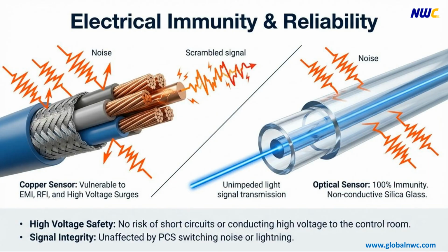Copper-based sensors are inherently vulnerable to electromagnetic interference and high-voltage surges, making signal distortion unavoidable. In contrast, optical sensors made from non-conductive silica glass provide complete immunity to external electromagnetic noise. Thanks to these physical properties, even in environments with lightning strikes or intense PCS switching noise, the system maintains perfect signal integrity without any risk of electrical short circuits. As a result, it ensures high-voltage safety while enabling highly accurate data transmission, significantly enhancing the overall reliability of the system.